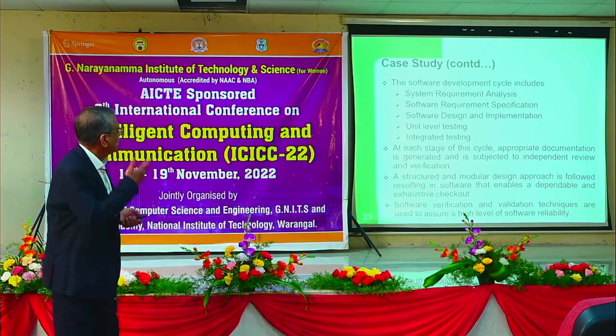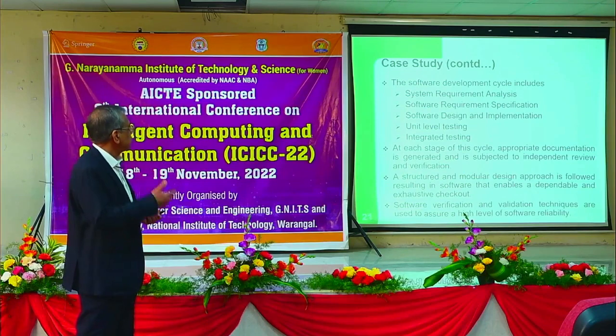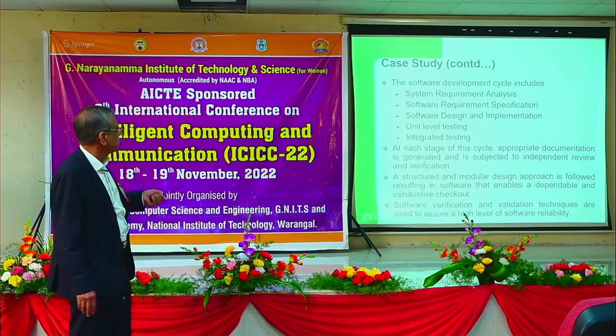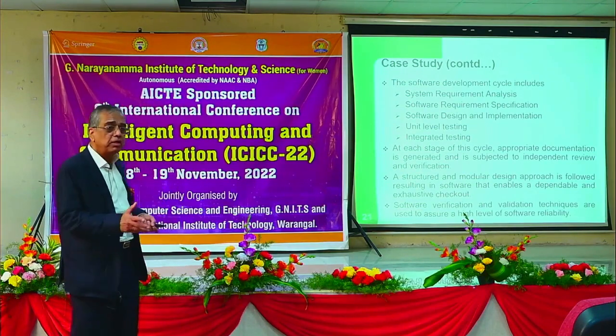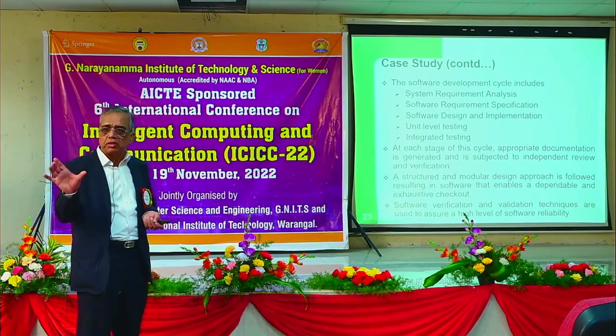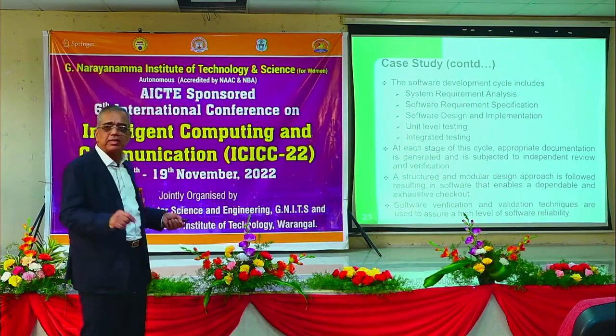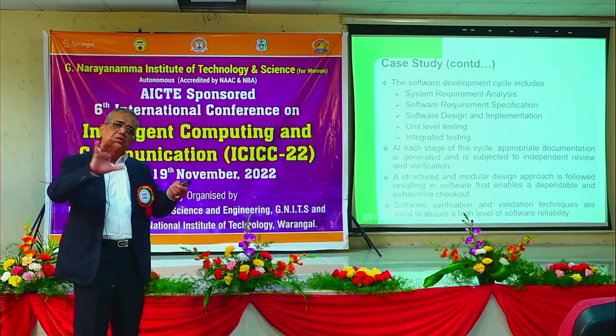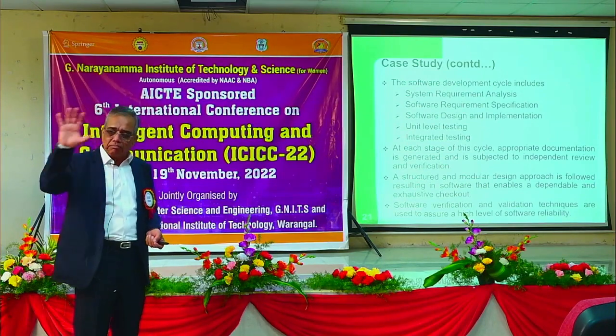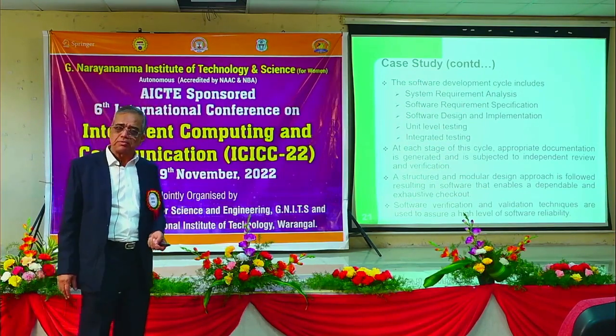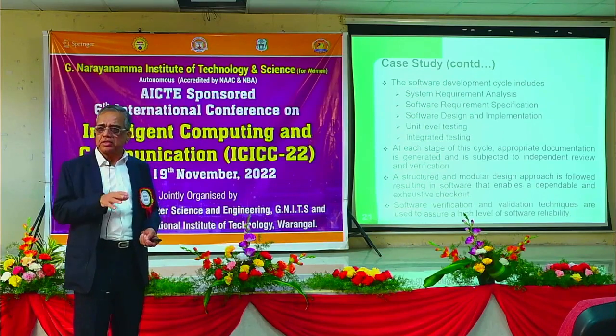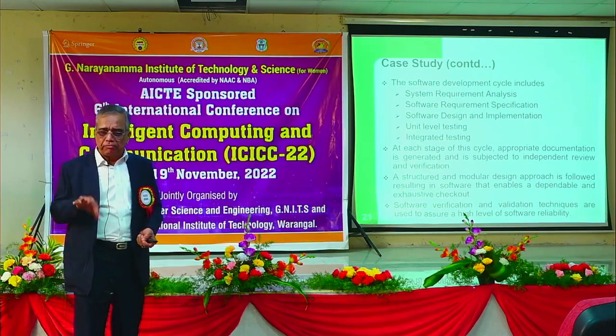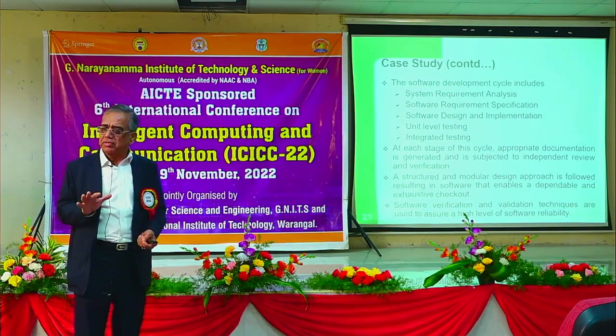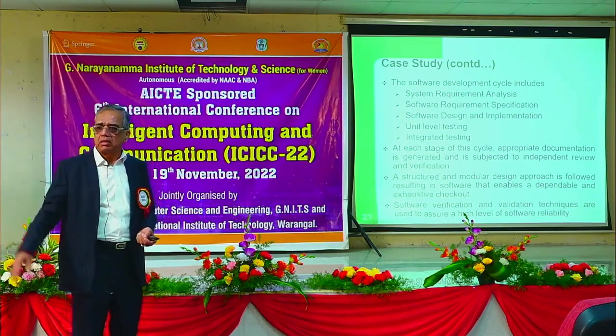The software development cycle I already told you: system requirement analysis, software requirement description, software design, implementation, unit level testing. Each software has to be tested independently, then you integrate it and test it. After integrating the software, you put it in the full scale prototype system and test all the functions, all the faults and all the malfunctions, and then see that it remains safe.